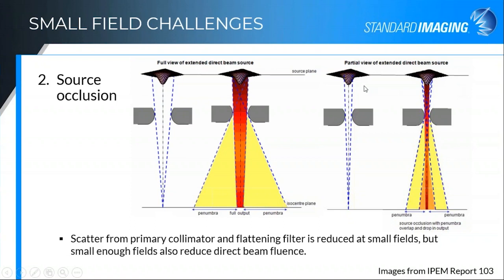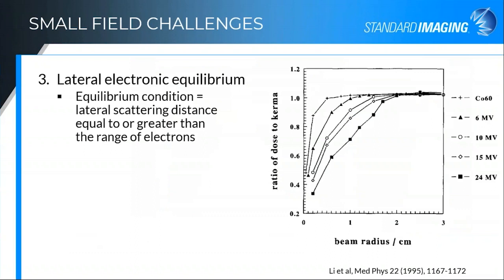Source occlusion is the next major challenge with small fields. With a larger field, you see the full source profile from where the beam is being generated and the target. Once you get down to these smaller fields, the view of the full source is truncated. That's what we call source occlusion. Both the scatter is reduced as well as the direct fluence from the target.